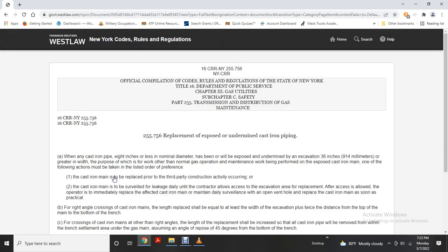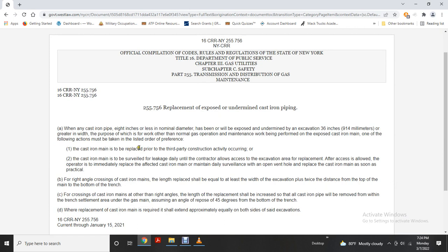Alright, replacement of exposed, undermined cast iron piping. When any cast iron main of 8 inches or less nominal diameter has been exposed by undermining excavation of 36 inches or greater in width, for work other than normal gas operation and maintenance work, one of the following actions may be taken, listed in order of preference. The cast iron main is to be replaced before the third party construction activity occurs. The cast iron main is to be surveyed for leakage daily until the contractor allows access to the excavation area for the replacement. After access is allowed, the operator immediately replaces the affected cast iron main. Maintain daily surveillance with an open vent hole and replace the cast iron main as soon as practicable.